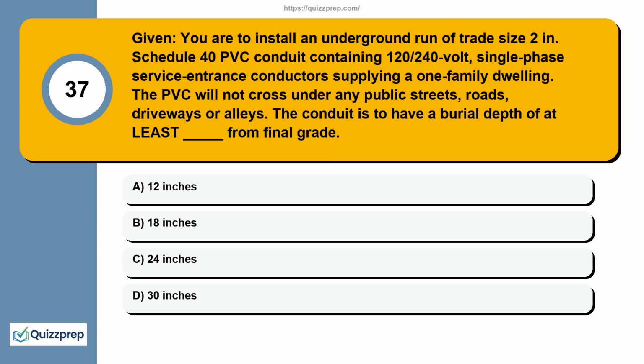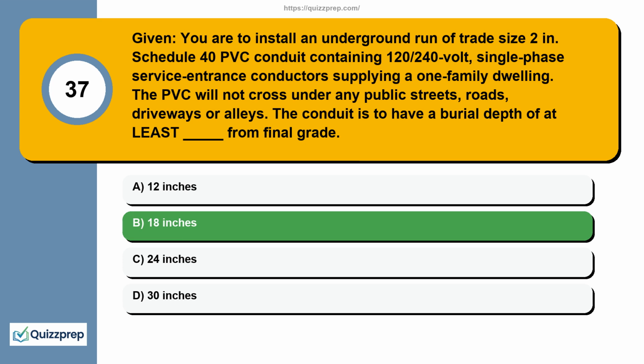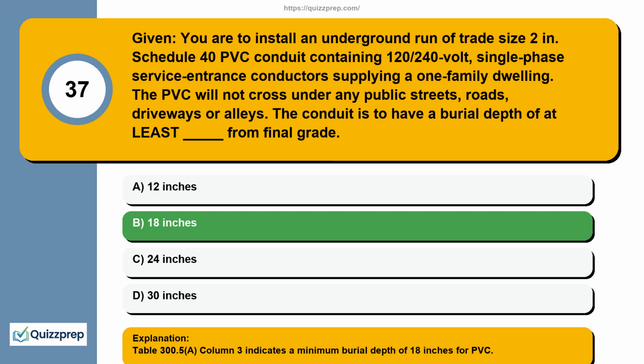Question 37. Given, you are to install an underground run of trade size 2 inch Schedule 40 PVC conduit containing 120/240 volt, single-phase service entrance conductors supplying a one-family dwelling. The PVC will not cross under any public streets, roads, driveways or alleys. The conduit is to have a burial depth of at least what from final grade? 12 inches, 18 inches, 24 inches, 30 inches. Table 300.5(A), column 3 indicates a minimum burial depth of 18 inches for PVC.